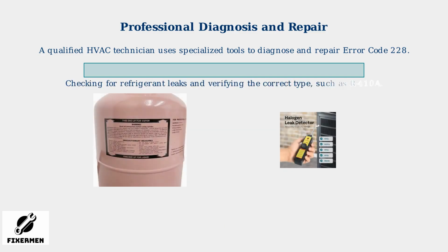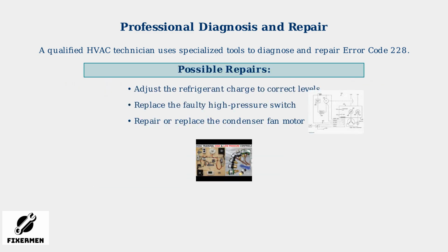The technician then checks for any refrigerant leaks using a specialized detector. They also verify that the system uses the correct refrigerant type, like R410A, to ensure compliance with regulations and proper system performance. Based on the diagnosis, the technician may perform several repairs. This could include adjusting the refrigerant charge to optimal levels, replacing the high-pressure switch if it's malfunctioning, or repairing the condenser fan motor to ensure proper airflow and cooling.